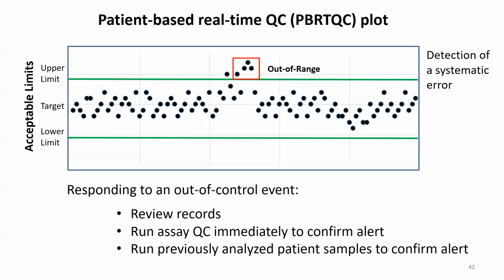So if an alert is received, the technologist should immediately review laboratory records to determine if there are any observable issues that need to be addressed and could be causing this alert. They should run assay QC immediately to actually confirm that there is a real issue. And they can always run previously analyzed patient samples to determine if there is a change in those patient sample results that would confirm the alert.